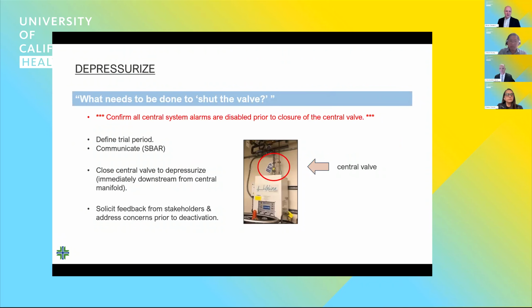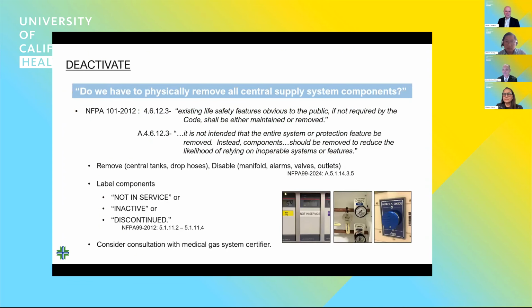Before you shut that valve off, in order to save yourself a lot of headache and heartache, you want to confirm that all the central system low pressure alarms have been deactivated. See Andy smiling because he lived this experience. And then finally, deactivation. This is a common question. Do we have to physically remove all of the central supply system components? And there's confusion around this. Some people, we've run into some people who say, well, we have to get rid of all the pipes.